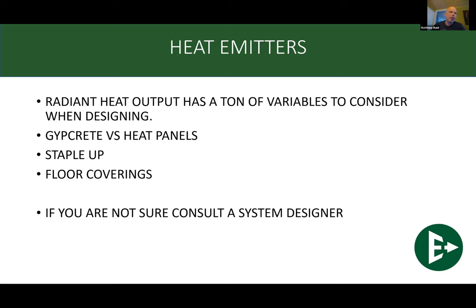You're usually talking about a subfloor, and then maybe you even have an additional floor on top of that before you get to your hardwood, tile, stuff like that. So it can take a lot to drive that heat through a staple up. It also usually requires warmer temperatures than a standard in-floor. If you're doing an in-floor with gypcrete, you can run anywhere from 90 to 110, something like that. Well, with a staple up, you're definitely going to want to be getting into the warmer temperatures of the 120 to make sure you're getting enough heat into that area to drive it through there.